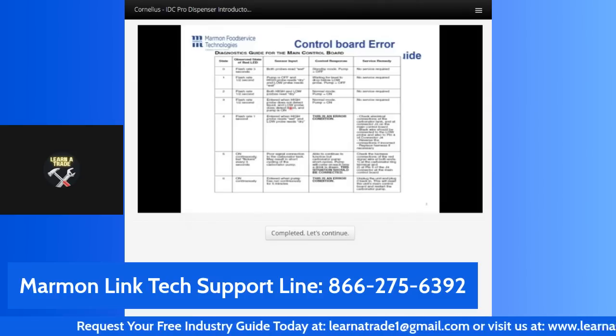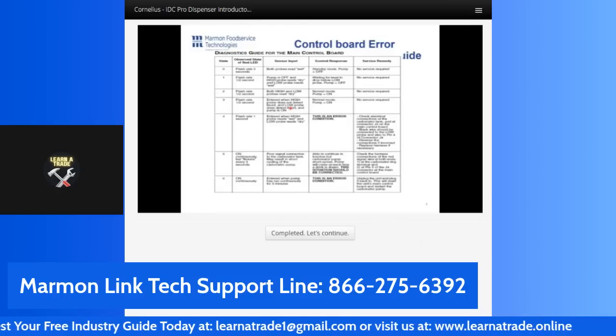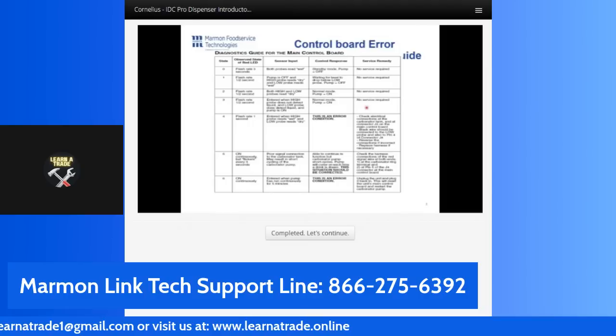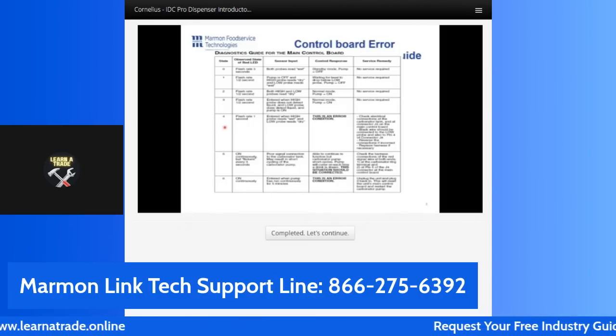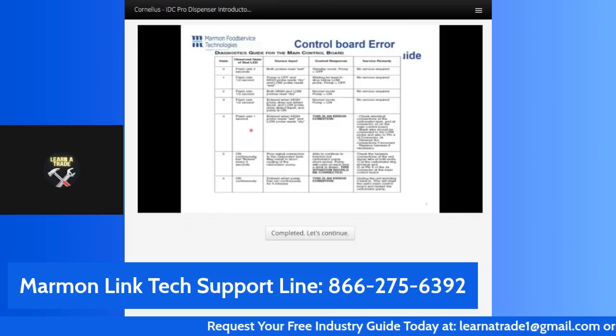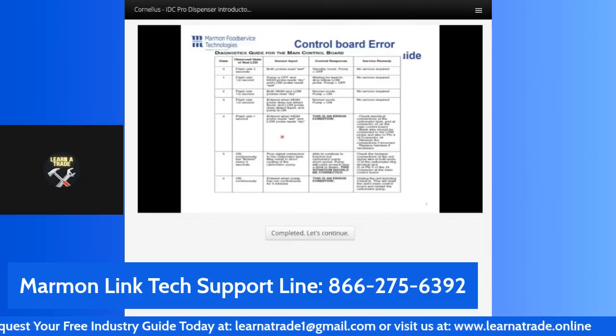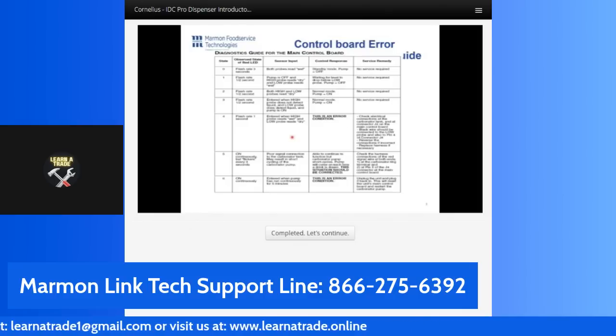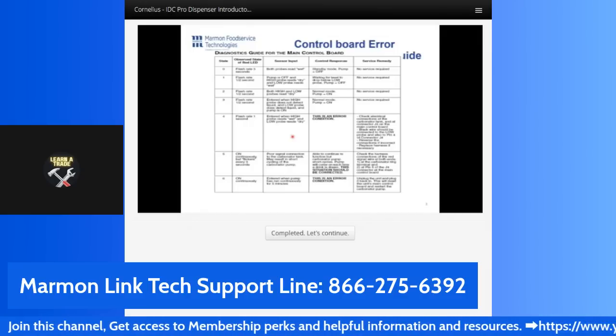So the low probe is covered. The board can see that. The high probe hasn't gotten covered yet. So it's still the pump on mode. And again, no service required. Moving on to status number 4. The flash rate of 1 second can be seen. And what that means is that the high probe reads wet where the low probe underneath it is reading dry. Now that doesn't make sense in a tank filled with water. So the board doesn't like that and it's going to go into an error mode and give a flash rate of 1 second. And there's a number of reasons for that.